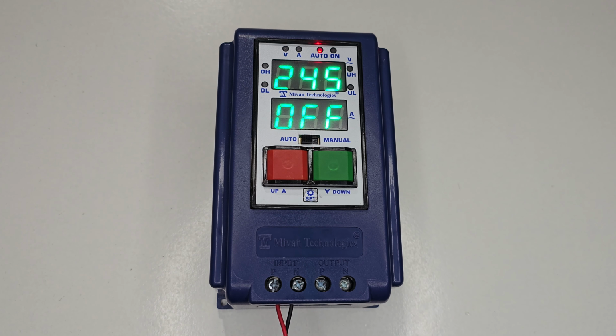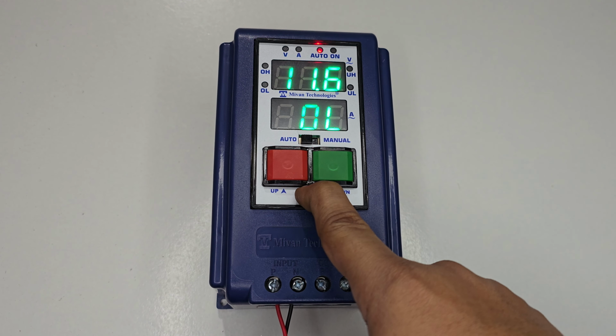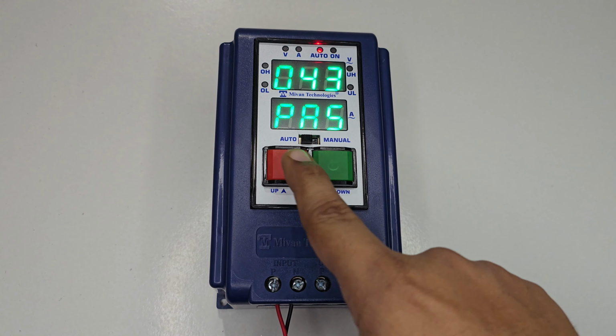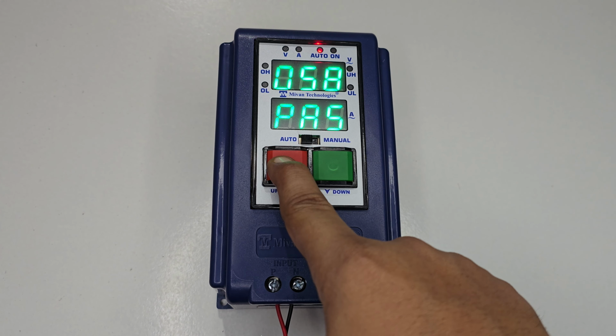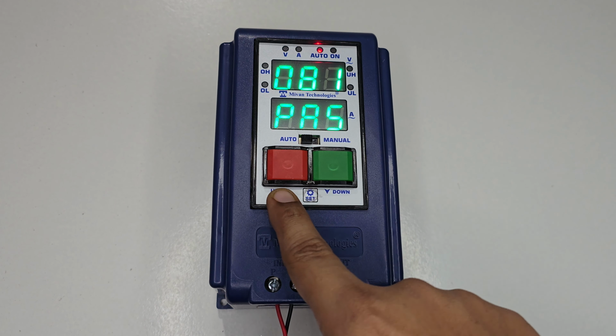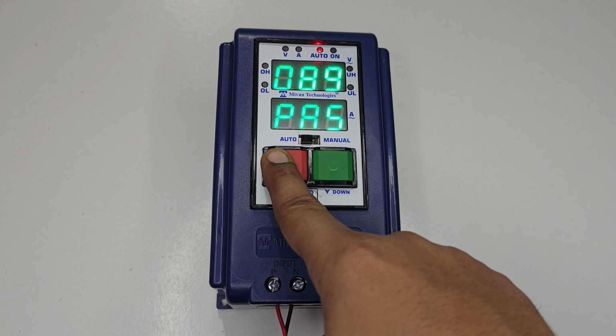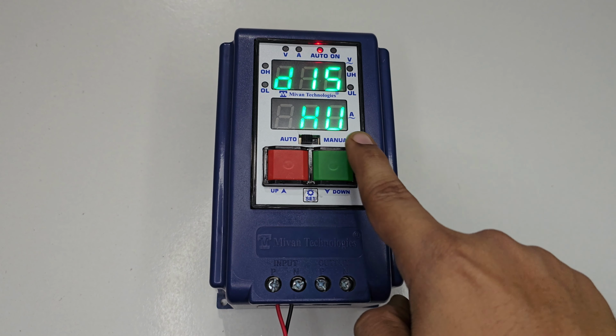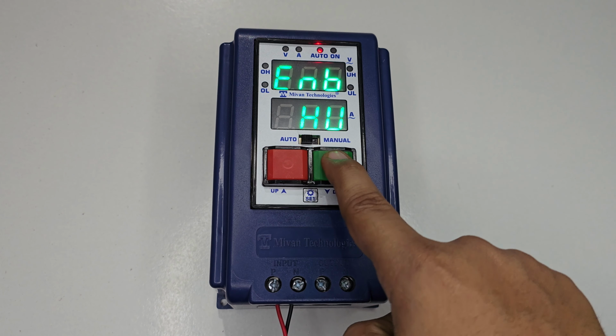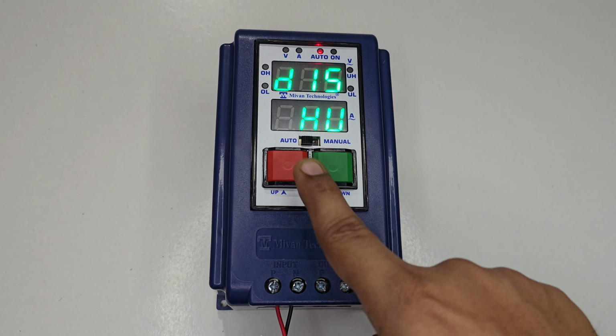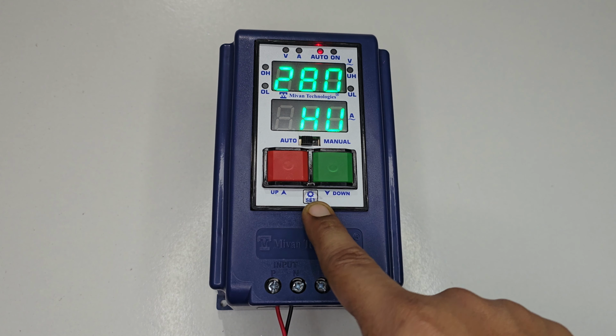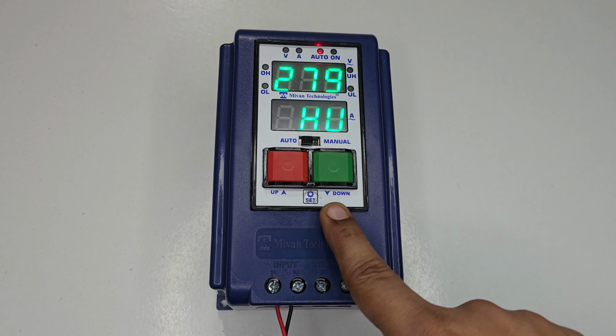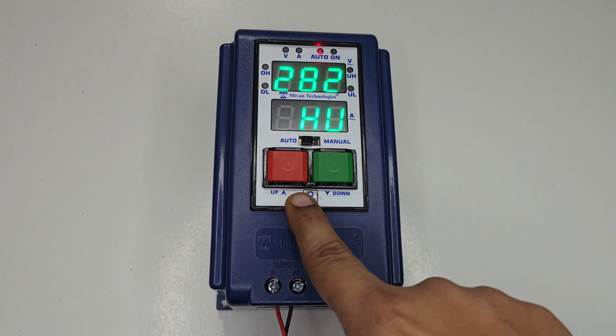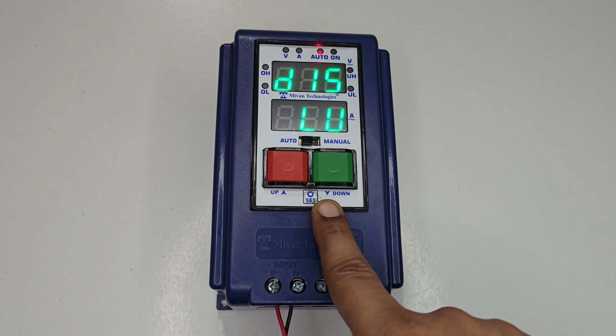Now I'll show you how to set the high voltage and low voltage cutoff limit. Press the set button for 5 seconds. Go to password 90. Press the set button. Here you can see a high voltage enable and disable option. By pressing up and down key, you can enable and disable the high voltage protection. Make it enable and press the set button. Here you can see the high voltage cutoff limit adjustable menu. By up and down key, you can adjust the high voltage cutoff limit. Set the high voltage cutoff limit and press the set button to store the value.